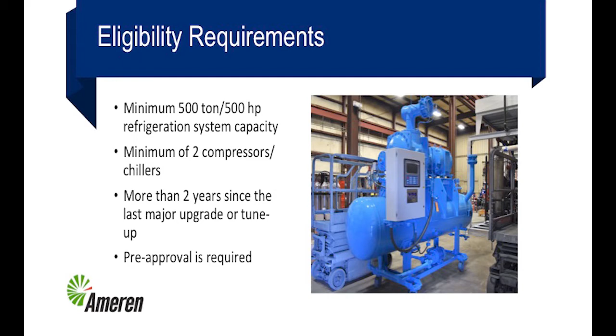More to the bottom line, the retro-commissioning for industrial refrigeration can help reduce operating costs, lower maintenance and equipment strain, and provide a plan for future upgrades or capital budgets. It also provides a report with savings information that can be used on custom applications or incentives. Custom applications historically have provided the biggest program incentives for qualifying projects. Some of the energy efficient measures are lowering condensing pressure, raising suction pressure, evaporator fan control, evaporator defrost settings, and compressor sequencing.